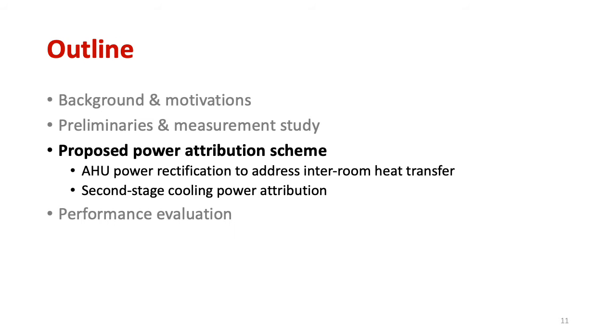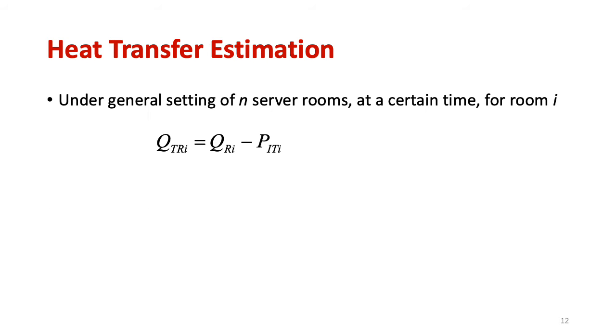From the measurement study results, we know that we can address the heat transfer problem and the second stage cooling power attribution problem separately. To address the heat transfer problem, we need to estimate the amount of heat flowed between any two rooms. We consider the problem under a general setting of n server rooms. At a certain time instant, the total heat transfer of a room is the difference between the total heat removed from the room and the IT load. It is also the sum of the heat transfers with all other rooms.